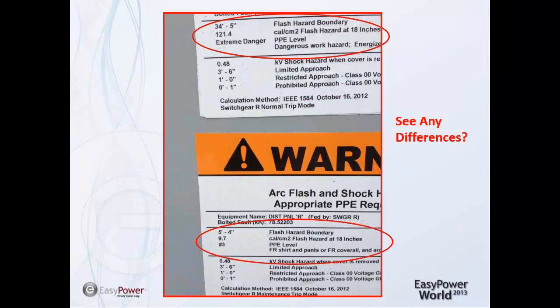This is one of the examples where we really have a major impact on personnel safety, and it makes it easier for our maintenance people to do these activities, because in a lot of cases we get the incident energy down to even a number 2 PPE level, which for us is less than 8 cals per centimeter squared.